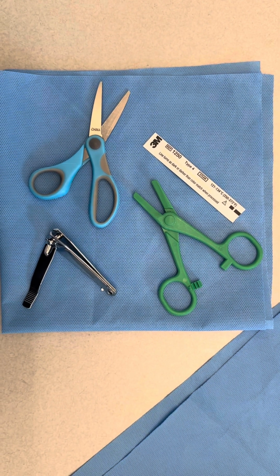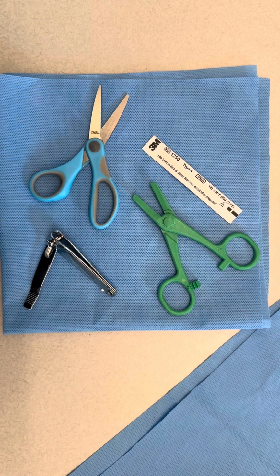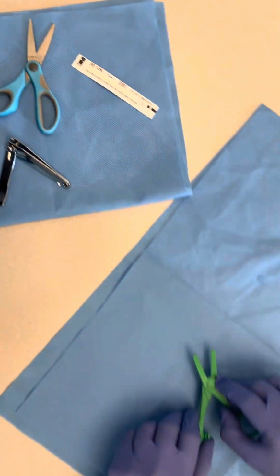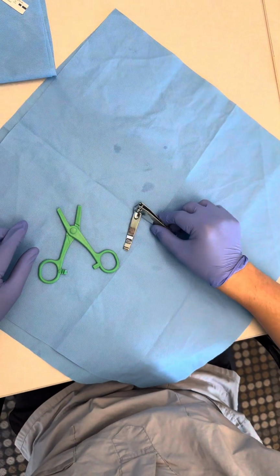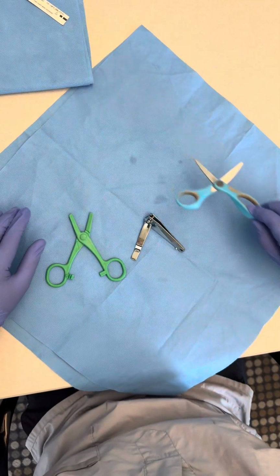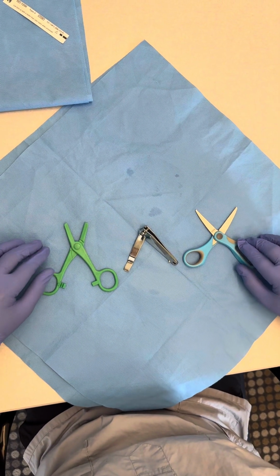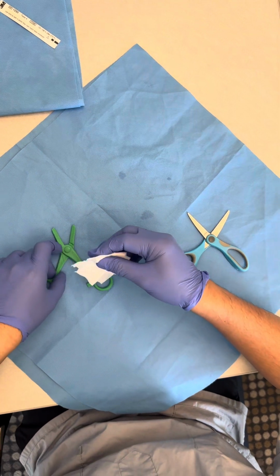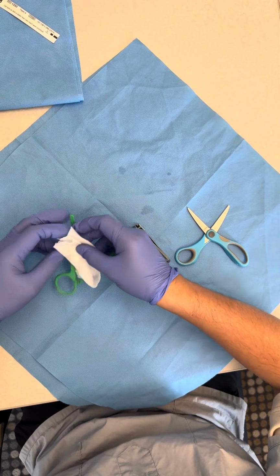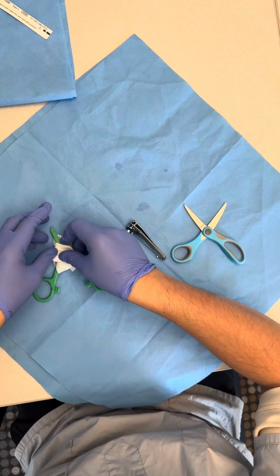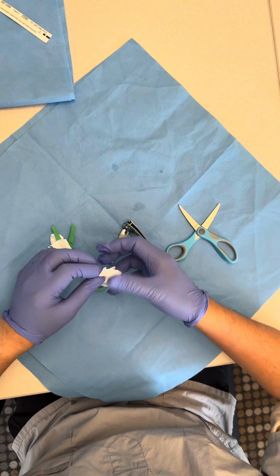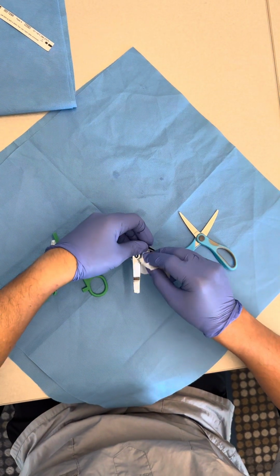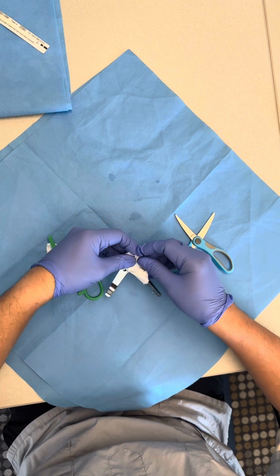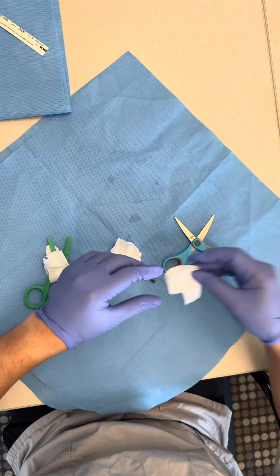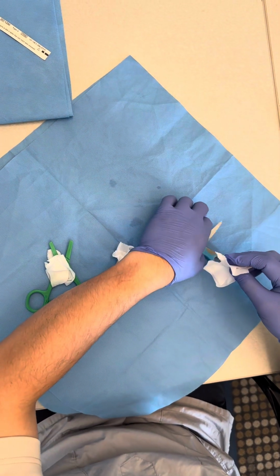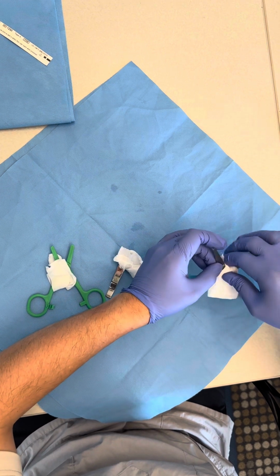In this next video, we will demonstrate the correct method for preparing and wrapping instruments for autoclaving. Sterilizing the instruments is essential to maintaining infection control in any healthcare setting. Today, we'll show you how to properly prepare, open, and wrap instruments to ensure they are sterilized effectively. To ensure thorough sterilization, it is important to open all hinges of instruments such as scissors or clamps so that the steam can reach every surface. Here we open the scissors, making sure the blades are spread apart. This step is critical to prevent any trapped microorganisms.